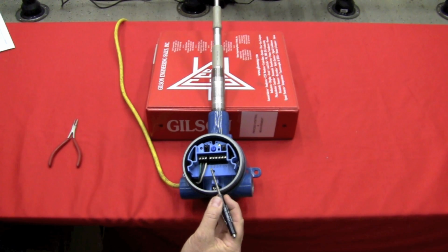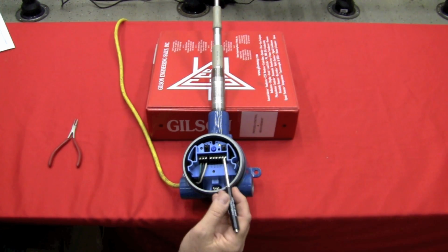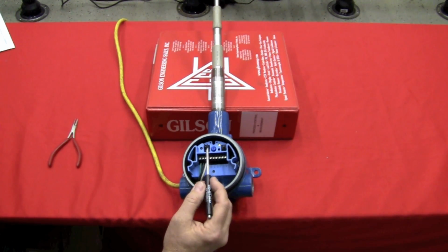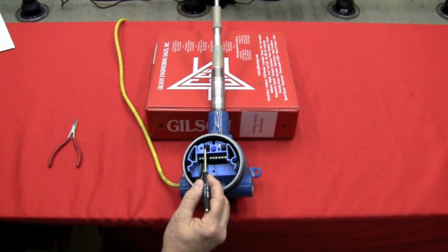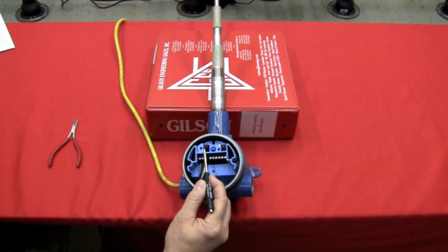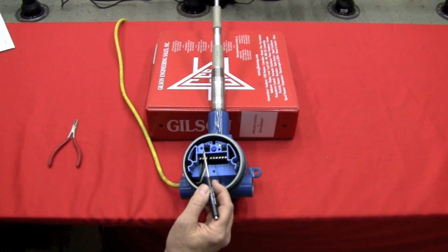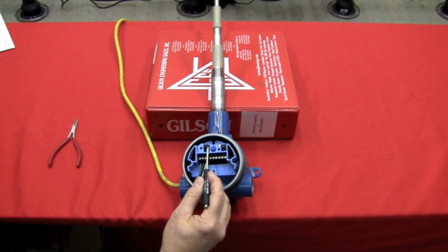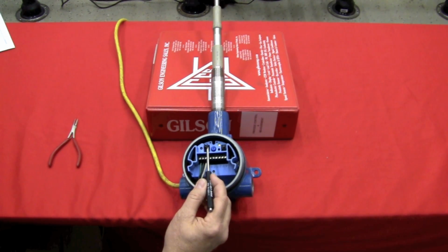Across here is our 5 amp double pole, double throw relay. On the top left you'll see two jumpers. The left-hand jumper is for your time delay, and we can delay our unit from going into alarm or coming out of alarm based upon the position of that jumper. The inside jumper here is your jumper for high-level fail-safe or low-level fail-safe. This unit can be used for high-level applications and or low-level applications.